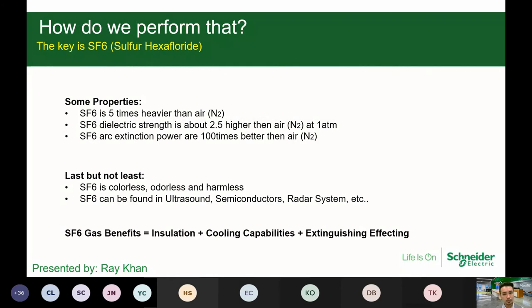Generally, SF6 gear has some key properties. The SF6 gas is pressurized, and it is five times heavier than normal air. It has a high dielectric strength compared to air. So all in all, its key purpose is to act as a very good form of insulation. SF6 also has the ability to extinguish the arc when it occurs, and in events when heating occurs, it has very good cooling capabilities.